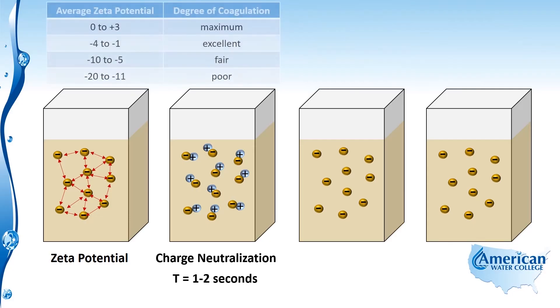Charge neutralization takes one to two seconds to occur, so once we rapidly mix the coagulant into the solution, within one to two seconds we've achieved charge neutralization. There are different degrees of coagulation, which is how we classify the extent of coagulation based on the zeta potential. You can see this chart in the upper left-hand corner showing the different degrees: maximum, excellent, fair, and poor. Starting at the bottom, poor coagulation would be a zeta potential in the range of minus 20 up to minus 11 millivolts.